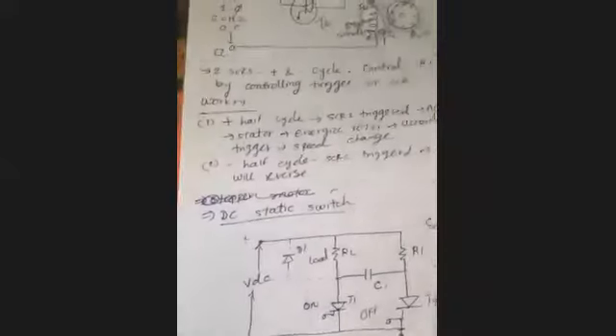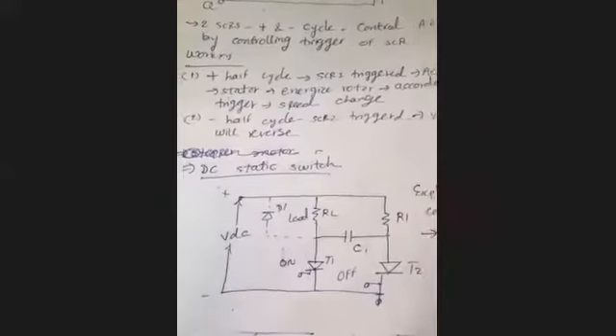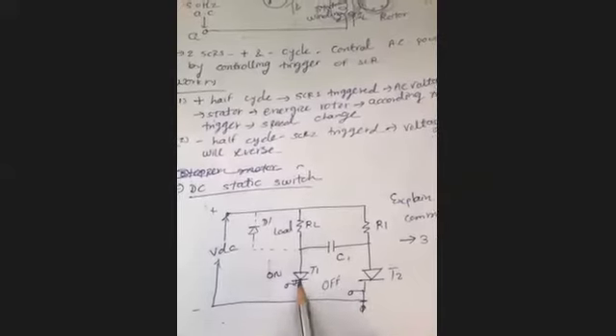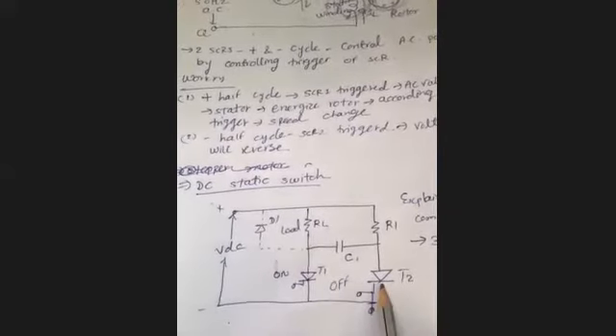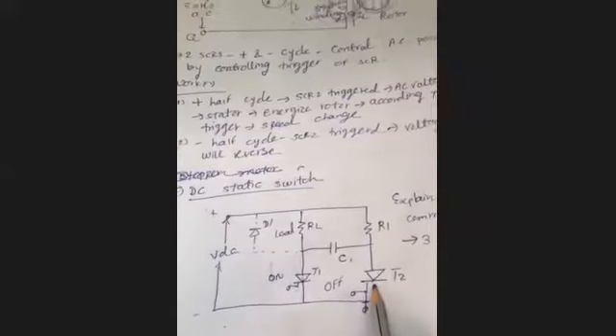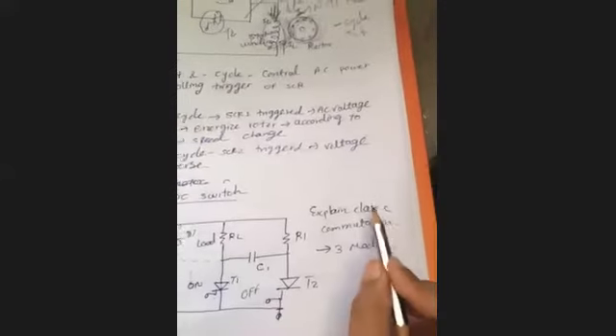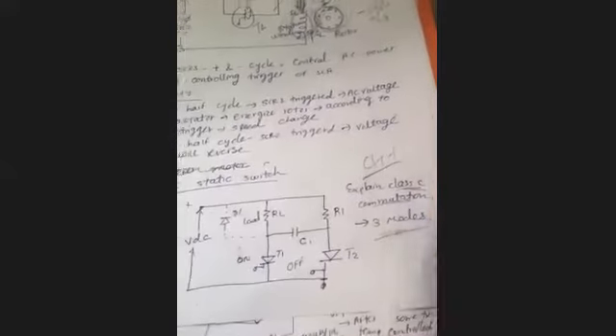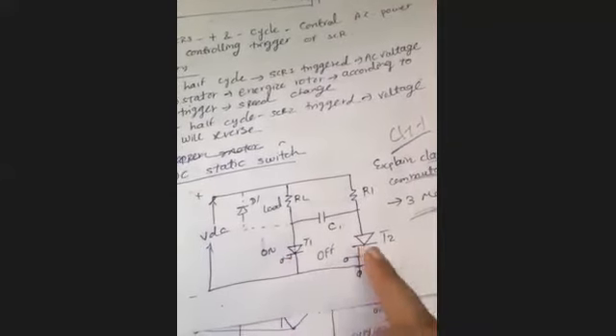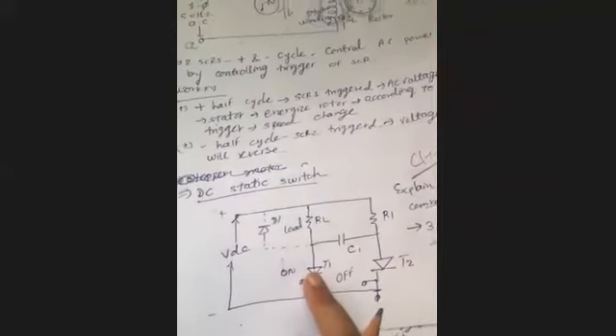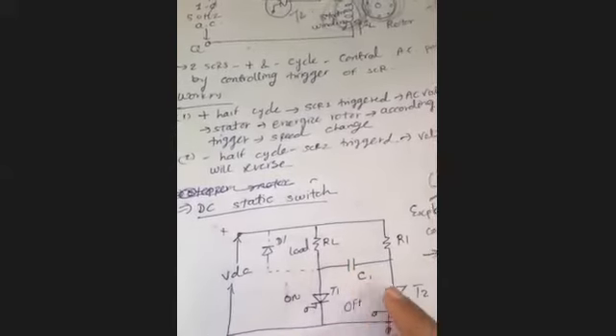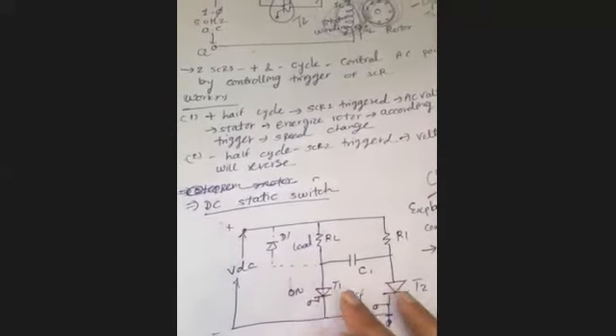The next type is the static switch. It uses a capacitor and two SCRs — T1 and T2 — operating in alternate modes. This uses class C commutation. There are three modes: at mode 0, the SCR is off; at mode 1, T1 is on; at mode 2, T2 is on; at mode 3, T1 is on again. The current direction determines which SCR conducts.